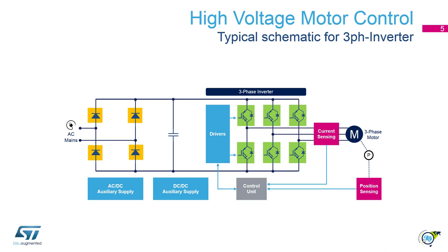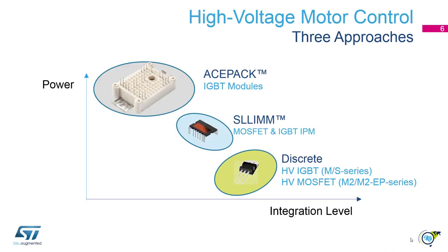In this typical schematic of a three-phase inverter we see the blocks from the previous slide now put into circuitry. For instance, we see on the left side a single-phase mains input using four diodes. In the center in blue we have the drivers. On the right side in green we have the output stage using IGBTs. In ST we have three approaches to form this output stage.